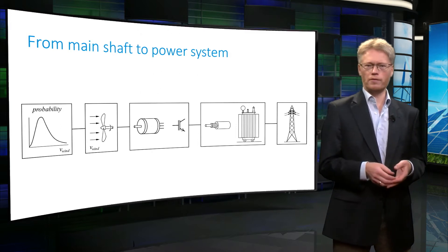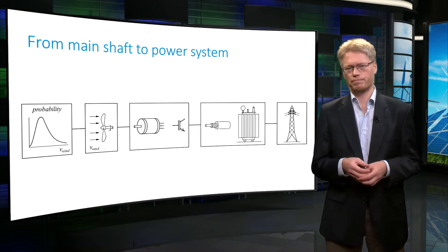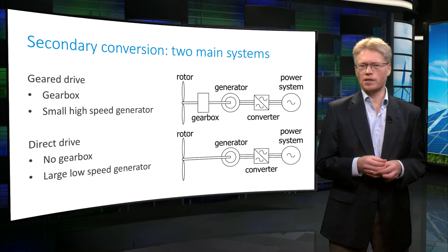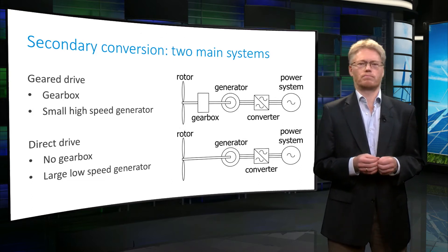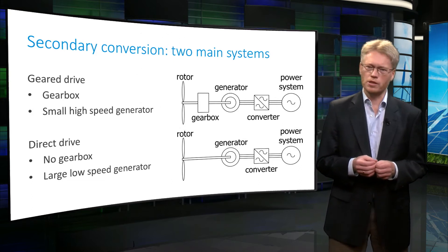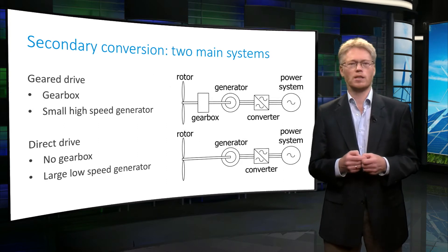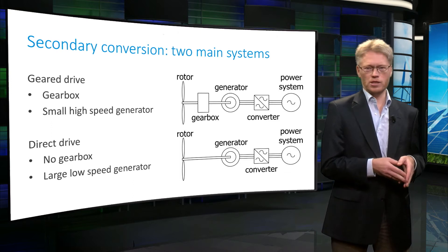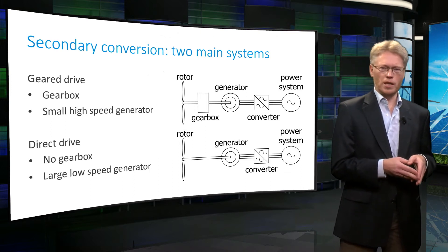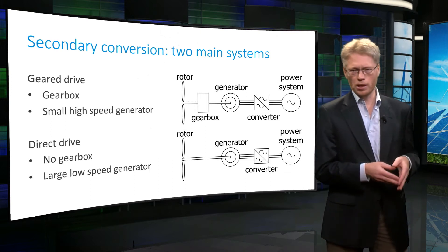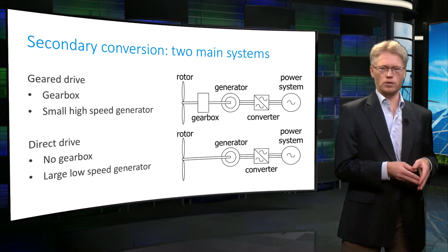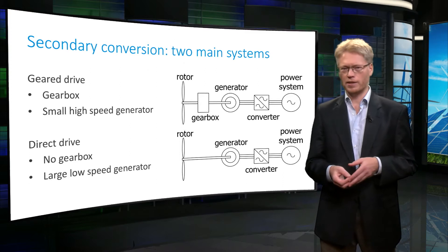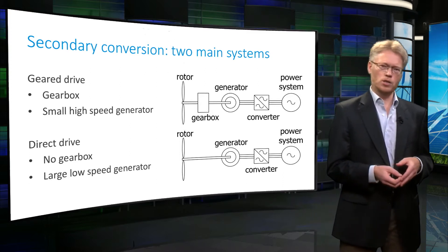First we will have a look at the generator system. In wind turbines, different generator systems are applied. The most important difference is between geared drive systems and direct drive systems. In geared drive systems, the mechanical speed of the main shaft is increased by a gearbox to a speed of roughly 1500 rotations per minute, and then a high speed compact generator converts the mechanical power into electrical power.